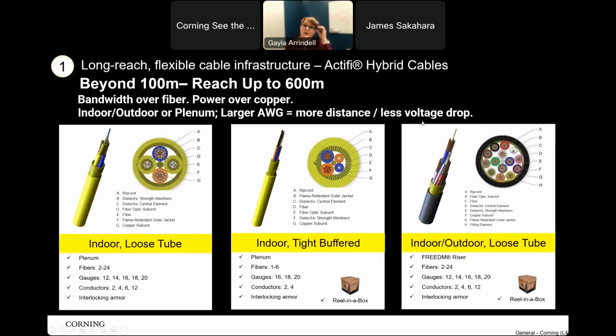So first I'll talk about the Actifi hybrid cables. With copper cables today that deliver PoE, the one big limitation is that you can only go 100 meters. After that you need a switch because you can't utilize typical category cable beyond 100 meters. Using these Actifi hybrid cables with fiber, you could literally go several kilometers, but when you combine the fiber and the power, we can reach distances up to 600 meters - 6 times further, giving a lot of versatility to get to those edge devices.